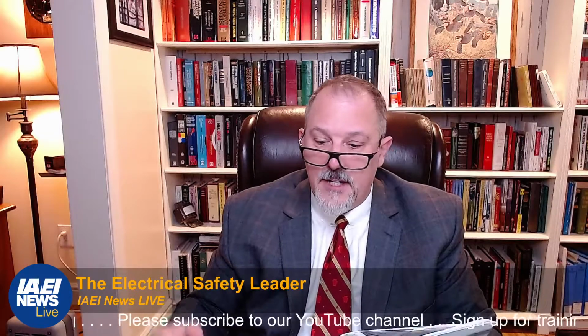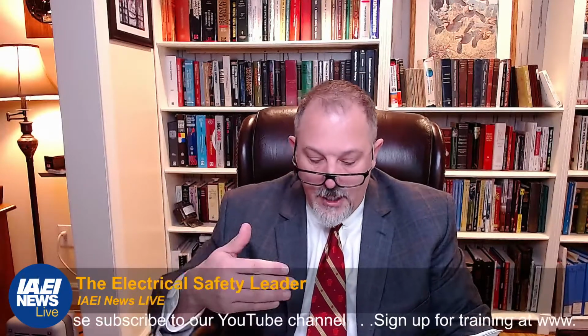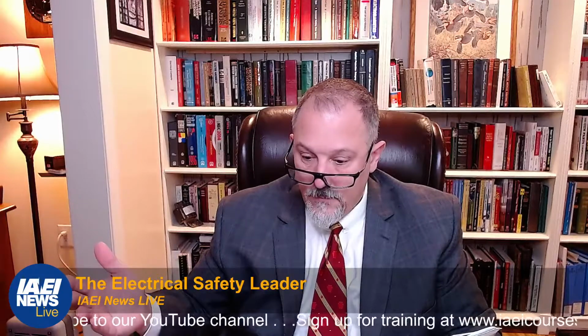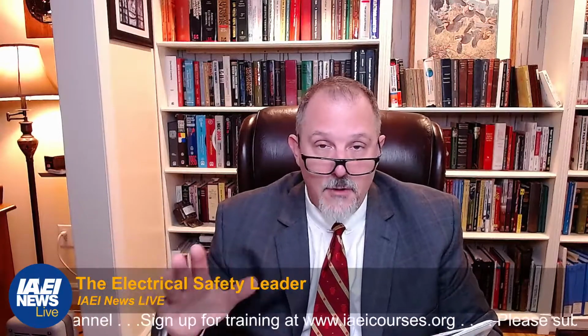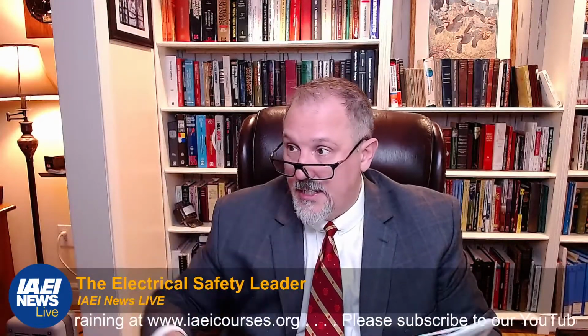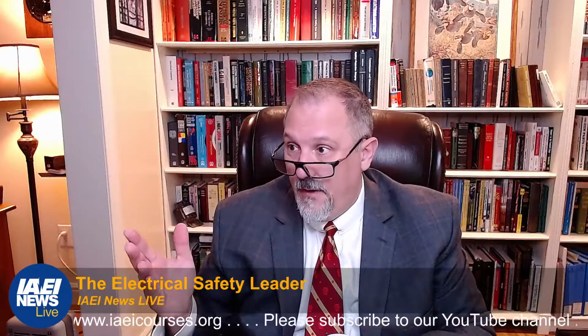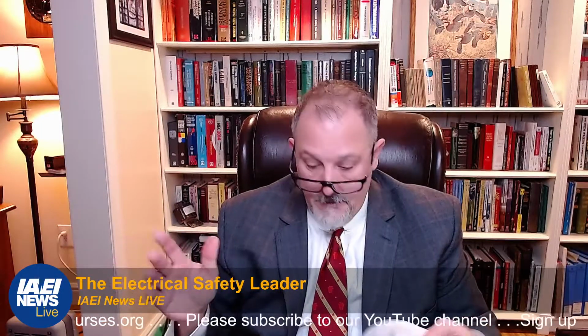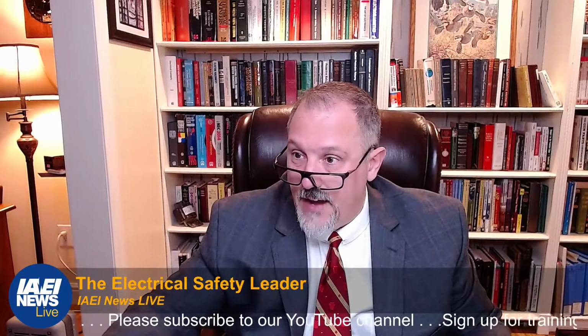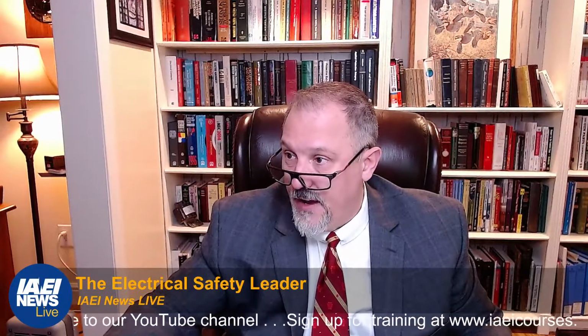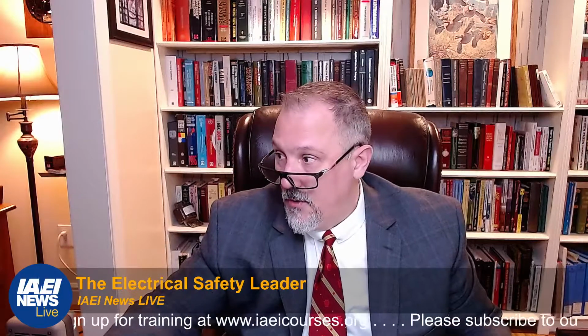All of those, you meet all of those. And then the estimate of likelihood of occurrence of an arc flash event for operating a circuit breaker in those normal conditions, likelihood is none. So there's no likelihood of an arc flash event from just turning a breaker on and off if it meets all of these conditions. Now, they changed that. And if I go to table 130.5, let's go to table 130.5. 130.5 still says normal and abnormal.